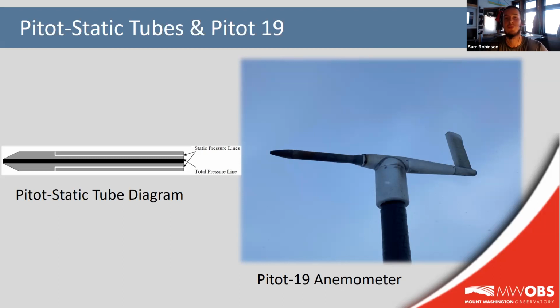The most basic explanation I can give of how a pitot-static tube works is that there are holes and tubes in the pitot tube, one at the end opening with an internal tube that's attached to it, which is the total pressure line, and then one or more holes on the side wall of the far end of the tube, perpendicular to the end opening, and those are also connected to another internal tube, which is the static pressure.